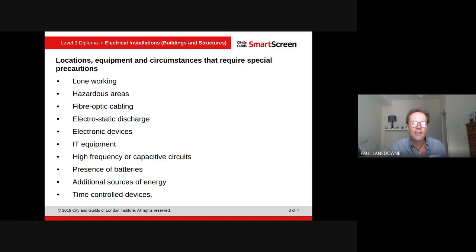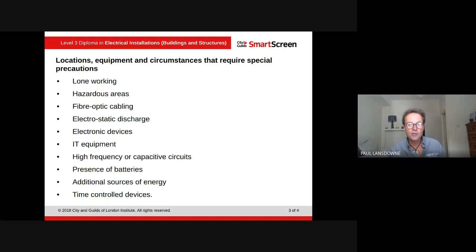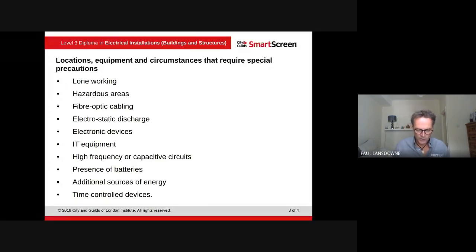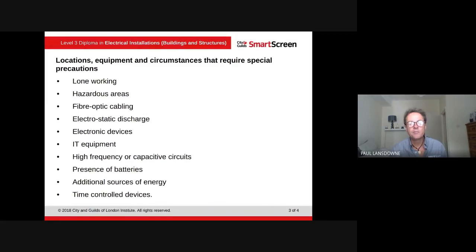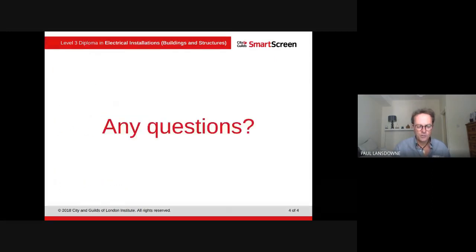High-frequency circuits can induce high voltages, and capacitive circuits and alternative sources of energy also need consideration — for example, solar panels or wind turbines. Time control devices are another hazard: you might work on an outside light, carry out safe isolation, and check the light is dead, but it has a PIR or time controller on it. It may only come on at five o'clock at night, so while you're working on it, it could suddenly become live. Check and make sure you have all the details.